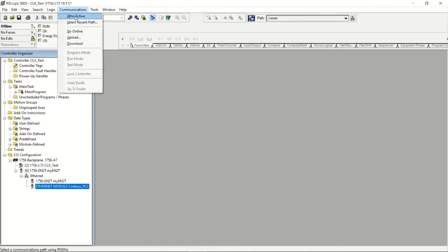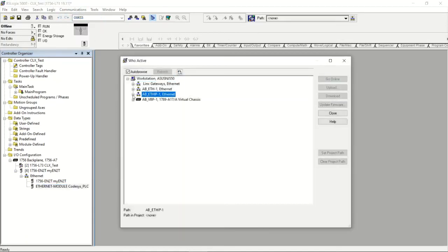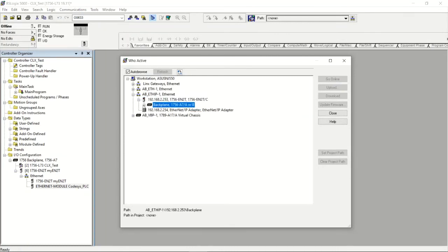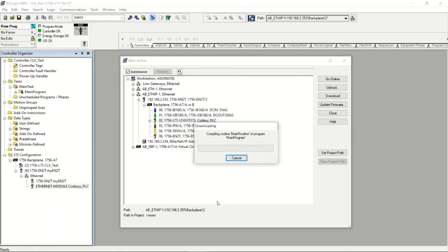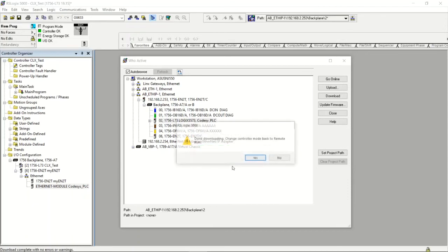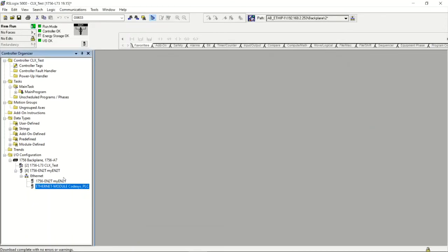All you have to do is download this to the ControlLogix. Downloading now. The giveaway — just like the green circles in CodeSys — is that there's no error triangle (the yield-sign icon) on the Ethernet card, and the I/O OK light is good, telling you that I/O over the network is functioning.